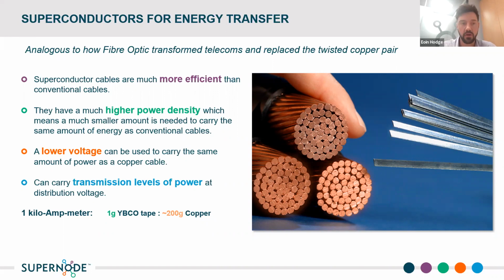To compare directly to copper - and it depends on application and design - we like to propose a ratio in terms of current density of 1 to 200. So in terms of cross section, one of the tapes you see on the screen per millimeter square can be 200 times smaller than that of copper. That's obviously very advantageous in terms of the size of cables, the leeway, consenting, and all that type of challenge that exists when high capacity copper needs to be integrated into the system. So we're very confident that when we look back in 20 years, we'll confirm that superconductivity has done for power transmission what fiber optics have done for telecom and the twisted copper pair.